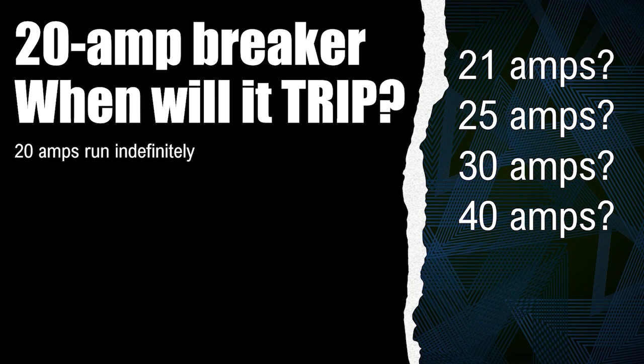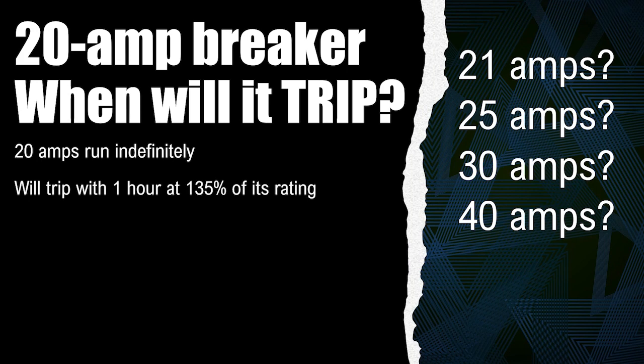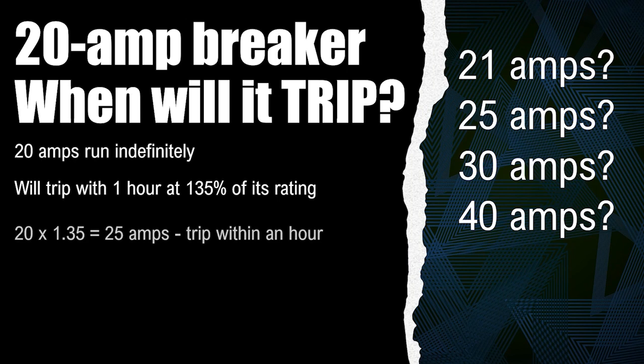This is not a paid promotion by Siemens by any means. But with that being said, if they were to send that breaker over to ETL and it tripped at 20 amps, they're not going to approve it. So the next standard is that it will trip within one hour at 135% of its rating — a confirmed trip within one hour at 135%. So if we have a 20 amp breaker, you would multiply that by 1.35, and it's allowed to run up to just under an hour at 25 amps.